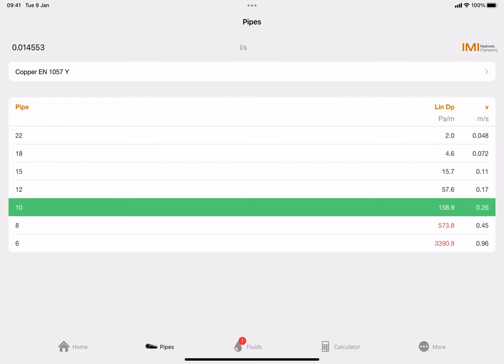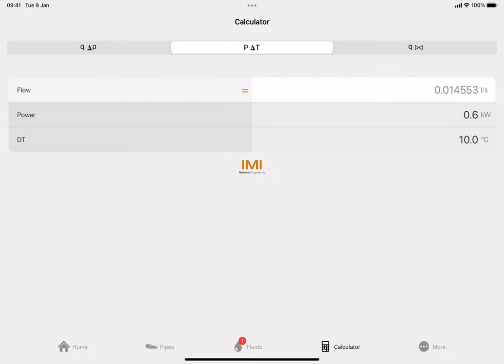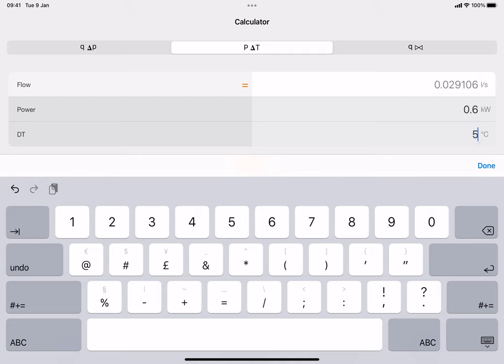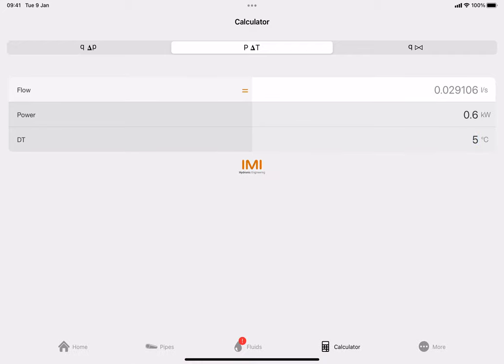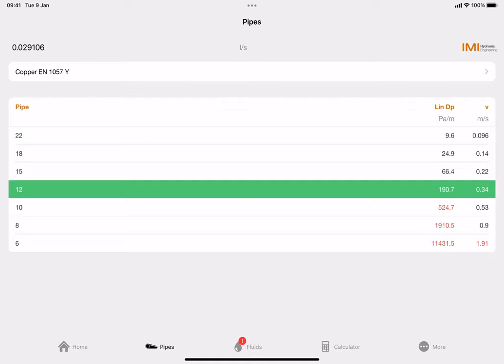If we want to ask: is that system going to be heat pump ready? Let's have a look. For a heat pump, 600 watts stays the same - the heat loss won't change - but let's say we're going to make it heat pump ready. We go back to our calculator and change Delta T 10 to Delta T 5, which doubles the flow rate as most of you will know. Click done, then go back to pipes. Look at 10 millimeter pipe work - if CIBSE states between 300 and 500 pascals per meter and we said 300, 10 millimeter table Y copper is giving us 524.7 pascals for every 1 meter of pressure drop.